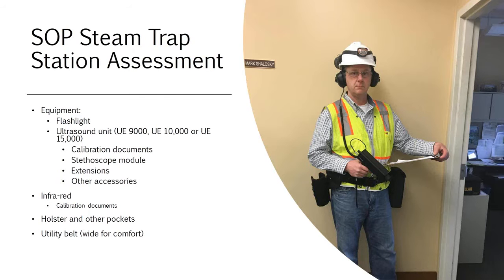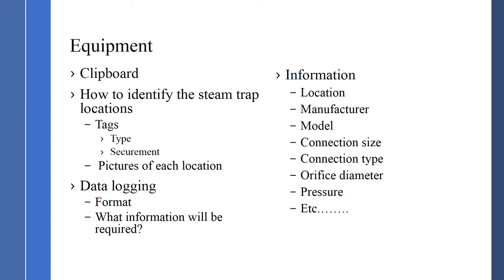Equipment also includes a clipboard and how to identify the steam trap location. When we do assessments, we need to understand how to get repair and replacement personnel back to that location. We're going to tag each trap — certain tags are acceptable, certain tags are not — and we identify what tags will be used and how to secure the tag to the steam trap, typically with a wire or chain method. Pictures of locations are also used today, with a defined numbering sequence and how to file pictures linked to the steam trap identification number.